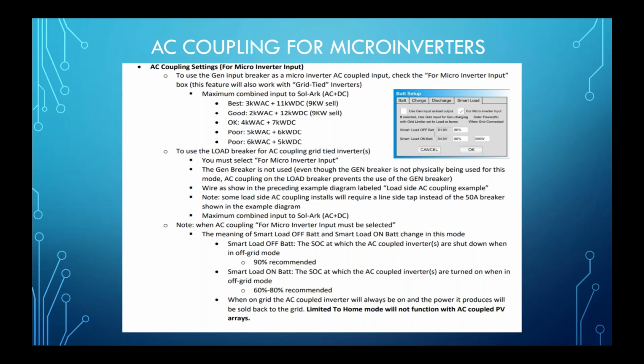The last note here is that when you are AC coupling, you have to go to the smart load and check the AC coupling box there. But when we do that, the smart load on and smart load off slightly change. Now the smart load off is the state of charge at which the AC coupled inverters are shut down when in off-grid mode, and the smart load on is the state of charge at which the AC coupled inverters are turned on when in off-grid mode. So for AC coupling, the smart load on and off now refer back to the AC coupled inverters.